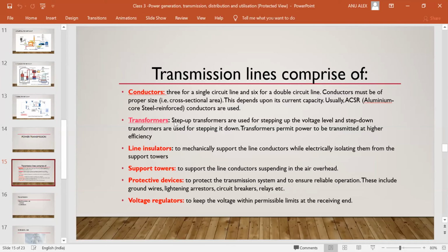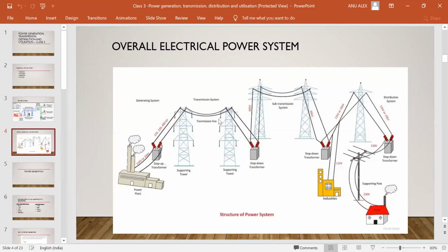The transformers you see here—like I told you, we don't want 132 kilovolt at the consumer side, so we step down this 132 kilovolt in stages, maybe to 66 kV or to 11 kV, as seen in this slide. The step-down transformer steps down the voltage from 132 to 66 kV, and again there is a step-down transformer that steps it down to 11 kV. These are all the step-down transformers occurring in the transmission system, because 132 kV is the voltage we transmit, and by stages we reduce it so the consumer finally gets it at only 11 kV or 415 volt.